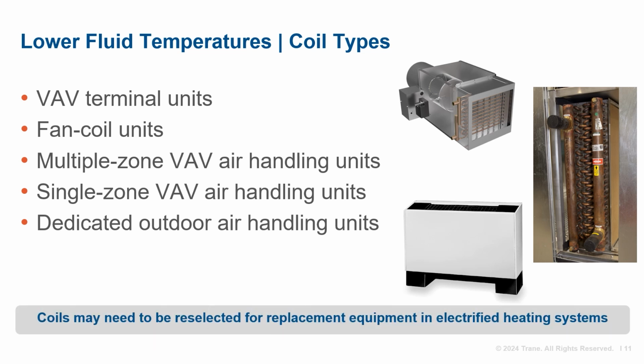As such, if equipment is aging out, a like-for-like drop-in may be inadequate, and some engineering time must be spent on a proper coil analysis using the new design conditions. Additionally, terminal units may have fewer coil geometry options and may influence the design hot fluid supply temperature more so than those inside the air handling units. On a positive note, many existing coils are already oversized.